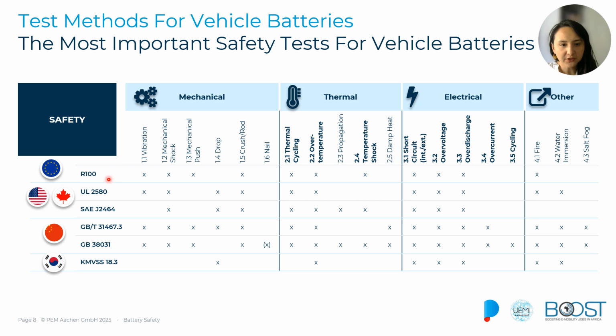So here on the left we have the different standards. And then we have split into the mechanical, thermal, electrical, and other categories of the different tests that the battery has to pass. On the first side we have the mechanical test. These include tests like, for instance, the vibration, the crush, nail penetrations, and so on. And the objective of this test is basically to simulate real-world shocks, impacts, and mechanical stress in our system, and guarantee that even in the presence of those, the battery remains safe.